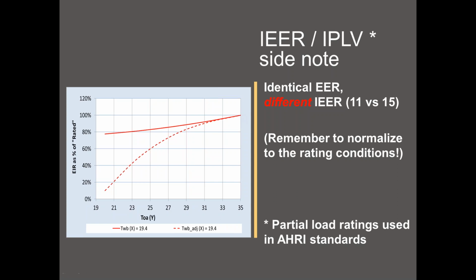And input power is actually the compressor power plus control power, which is normally very small, plus a fixed test condition fan power. So it includes all of the power elements at that particular test condition according to the AHRI standard. So an IEER of 11 derates to say 80% of the energy input ratio, or it's a number that reflects the amount of power for the capacity. An IEER of 15 has a hugely improved performance in power compared to the IEER 11. And so this is a big deal.